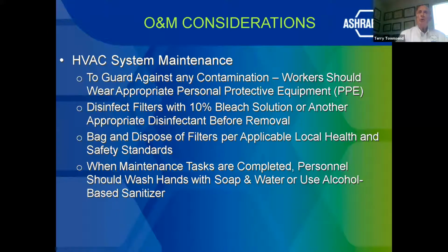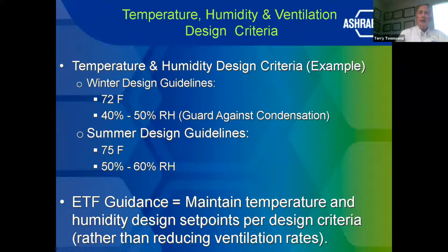Workers should wear appropriate personal protective equipment, disinfect filters with bleach, bag and dispose filters, and when maintenance tasks are completed, personnel should shower, wash hands, and use alcohol-based sanitizers. As an example here, they gave 72 degrees for winter design conditions, 40 to 50% relative humidity to guard against condensation, whereas in summer, 75 degrees F with 50 to 60% relative humidity. But the guidance is to maintain temperature and humidity design set points per design criteria without reducing ventilation rates. Ventilation rates are key and critical.